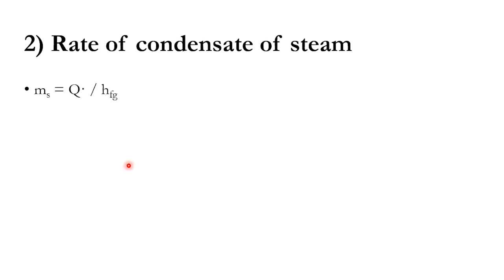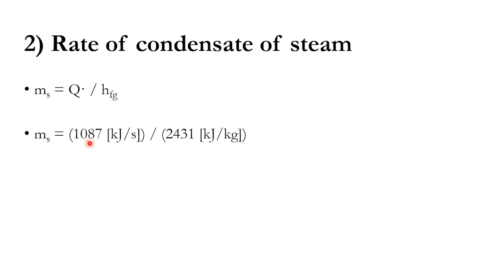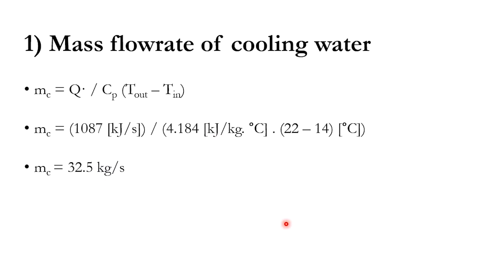For the rate of condensation of steam, since only latent heat is involved: Q = m · h_fg. With Q = 1087 kJ/s and h_fg = 2431 kJ/kg, the condensation rate is 0.45 kg/s. So for 0.45 kg/s condensation of steam, we need 32.5 kg/s of cooling water.